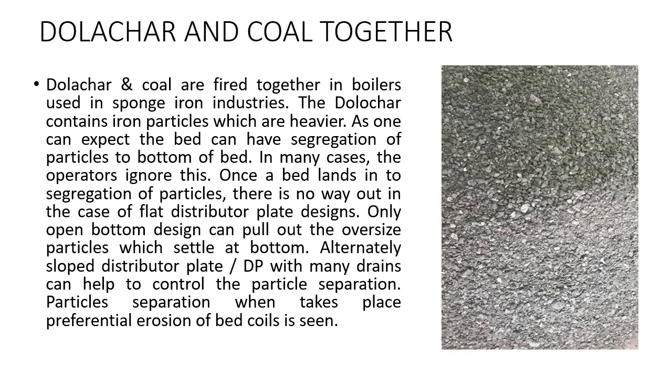Once a bed lands into segregation of particles, there is no way out in case of a flat distributor plate design. Only open bottom design can pull out the oversized particles which settle down at bottom. Alternately, a sloped distributor plate with many drains can help to control the particle separation. When particle separation takes place, preferential erosion of bed coils is seen.